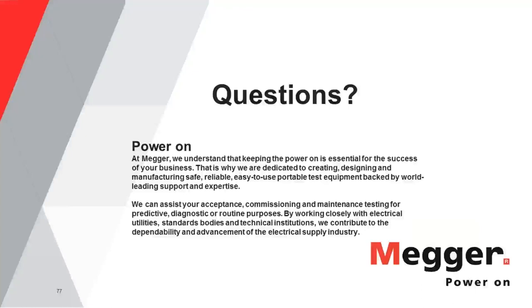Okay, let me think about that. For a given insulation resistance of a cable, is there a permissible margin that can be applied for pass-fail criteria? Very good question. The answer is yes and no. And I'm not trying to be funny there. It's a really good core question, because you will see assigned values in the literature. And if you're satisfying yourself, use your own judgment, because if you're a megohm lower, for instance, does that mean that the test item is no good?